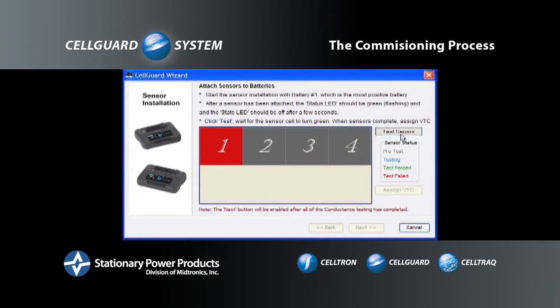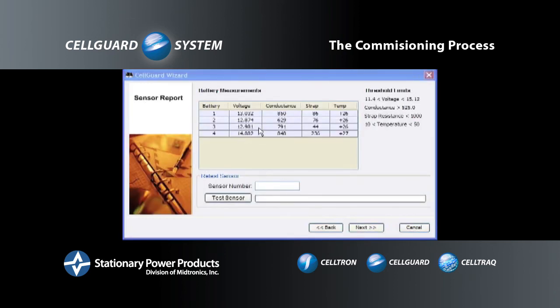The square for the problem sensor will go from red to blue, indicating the wizard is trying to commission the sensor again. When the square turns green, the sensor was successfully commissioned, and you can continue with the next sensor. This screen shows the initial readings generated during the commissioning process.